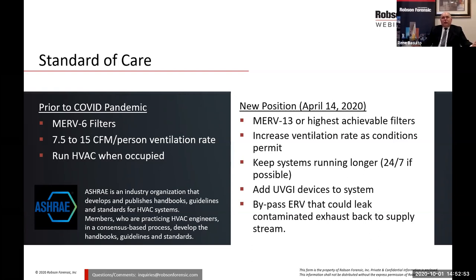The other item is that they're saying to keep the systems running longer, 24/7 if possible. Again, this is an energy issue. The longer you run it, the more it's going to cost. But the idea is to continue to move the air, to continue to dilute the indoor space, and to keep that air moving and cleaning it with the filtration and with whatever else you're adding to it. In the position paper, they actually recommend adding UVGI devices to the system. It's very silent when it comes to bipolarization. Don't know why, but that's the way the position paper stands. Bipolar is effective, perhaps not as effective.